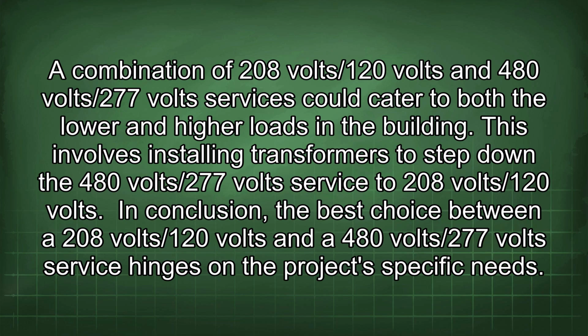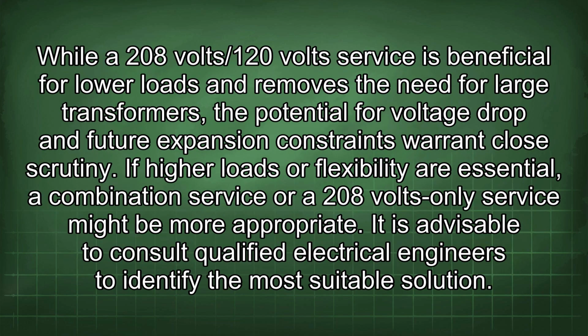In conclusion, the best choice between a 208 volts/120 volts and a 480 volts/277 volt service hinges on the project's specific needs. While a 208 volts/120 volt service is beneficial for low loads and removes the need for large transformers, the potential for voltage drop and future expansion constraints warrant close scrutiny. If high loads or flexibility are essential, a combination service or a 208 volts only service might be more appropriate. It is advisable to consult qualified electrical engineers to identify the most suitable solution.